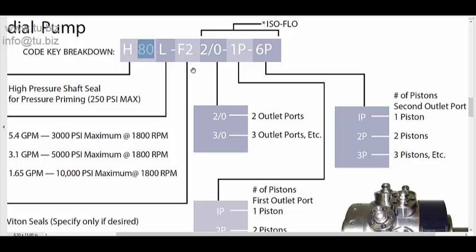For example, the H series, the H80, it has a total of seven pistons. You can have from one to seven outlets. You can have one through seven, but you can distribute the flow of the pistons depending on the outlets that you're going to have. So let's say you only want two. You can put only two outlets or you can put only three outlets, but you still have seven pistons available for flow.